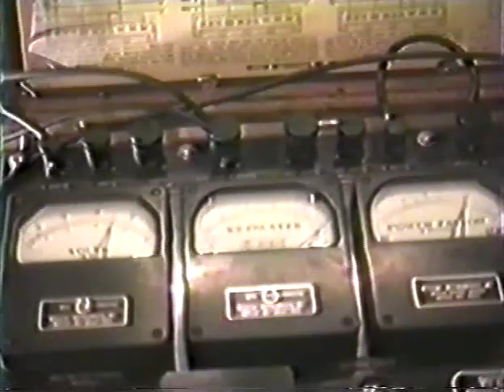Coming over to the next meter, this is a watt meter, and you divide it by half. You see it's reading 1 kilowatt on this one here, so divide that by 2, and you see that we're putting out 500 watts of actual measured power.